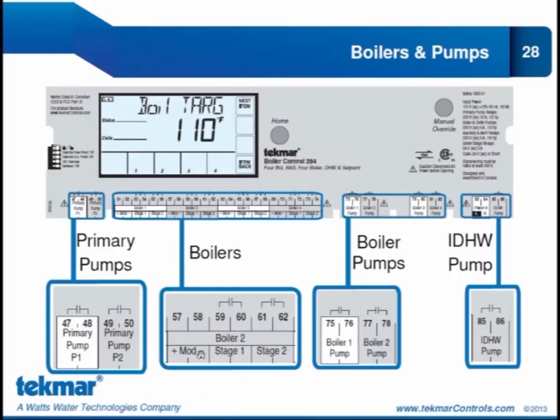We have the mod plus and minus terminals to connect to a modulating boiler. And we have the relays for the stage 1 and the stage 2 connections for the on-off boilers. And remember, we can use the stage 1 if our modulating boiler also requires an enable. We can control up to 4 boiler pumps as well. Now these are just dry contacts, so we don't provide power out to the pumps. It's just a contact closure. And here we can connect to our indirect domestic hot water pump.